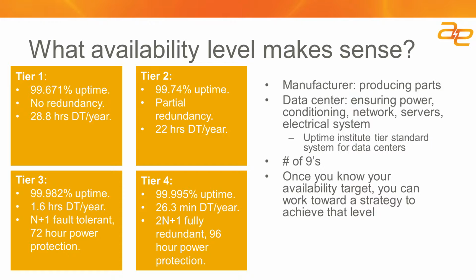99.995% availability would be considered 4 nines of availability. As we move from Tier 1 to Tier 4, at Tier 1 we have 2 nines of uptime with essentially no redundancy required, and up to 28.8 hours of downtime within a year. Moving to Tier 4, which has 4 nines of uptime, downtime drops from 28.8 hours all the way to 26.3 minutes.